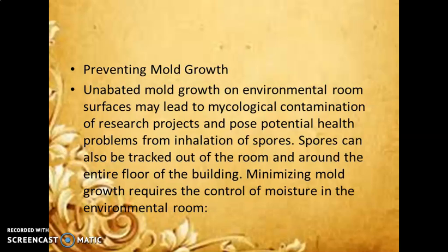Unabated mold growth on environmental room surfaces may lead to mycological contamination of research projects, and it may pose potential health problems due to the inhalation of those spores. The spores can also be tracked out of the room and around the entire floor of the building. Minimizing mold growth in the cold room requires control of the moisture in the environmental room. So we can prevent the mold growth in the cold room.